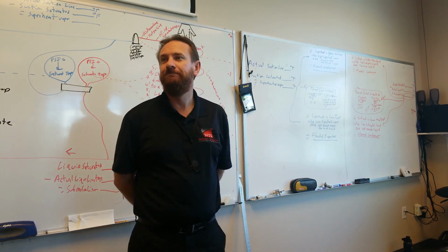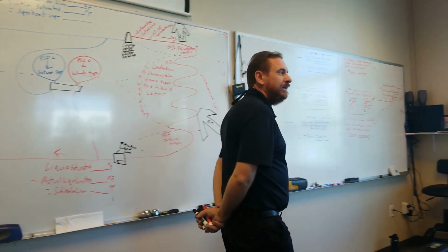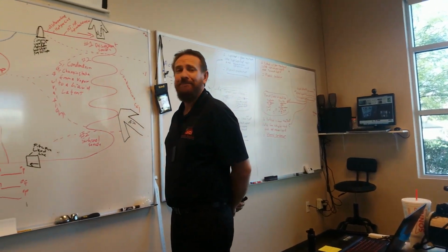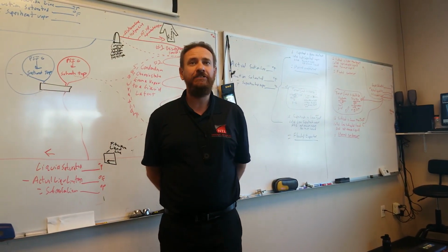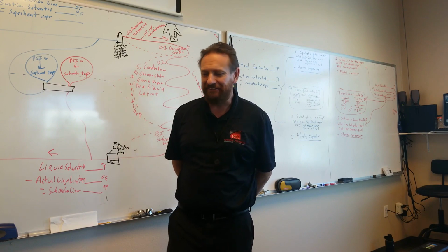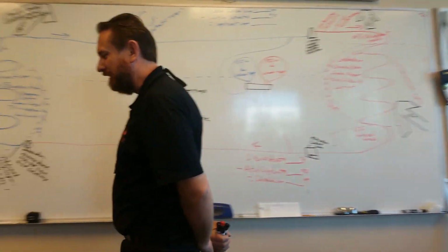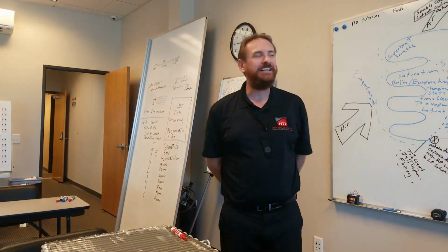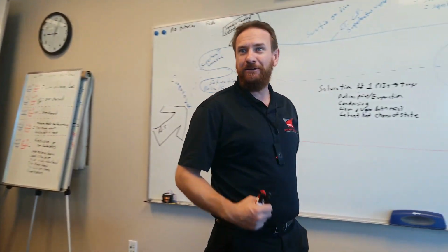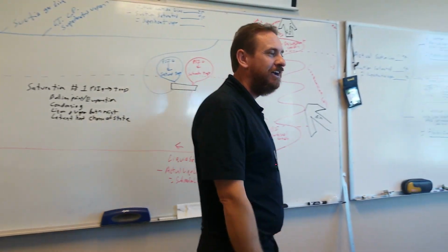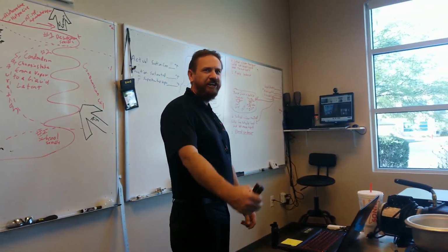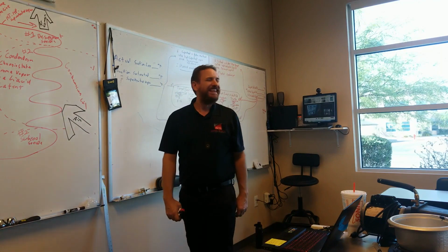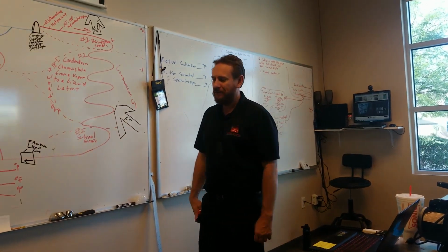Oversized. It's oversized. When it's 115 degrees outside, that unit should be maxed out. It should be on its whole way. When you're passing somebody on a 2-lane road, you have it floored to get around them. It's not like saying, I'm going to really need to goose it to get around this car, I'm going to give it 3/4 throttle here. Right? That is an oversized AC for sure.